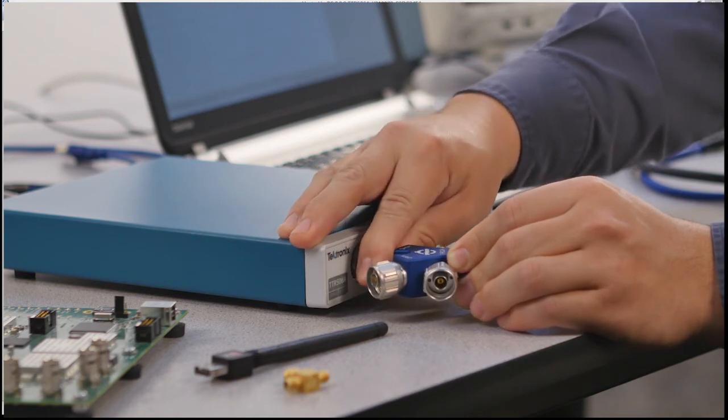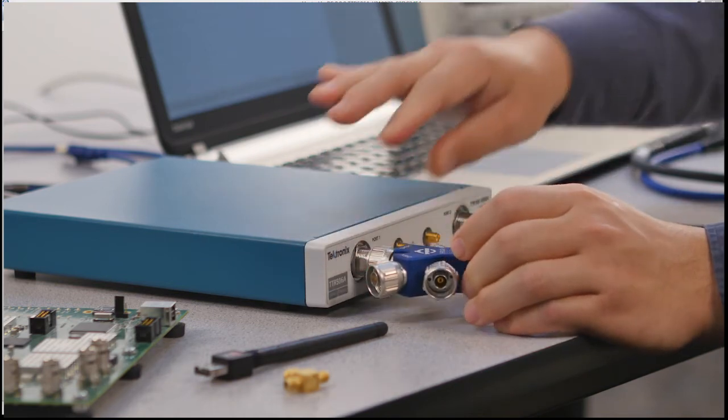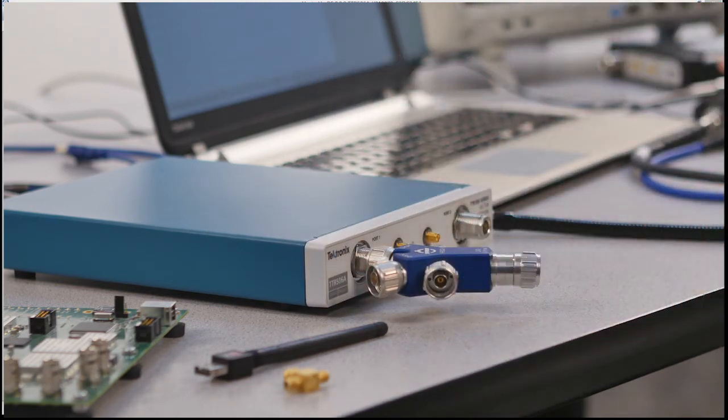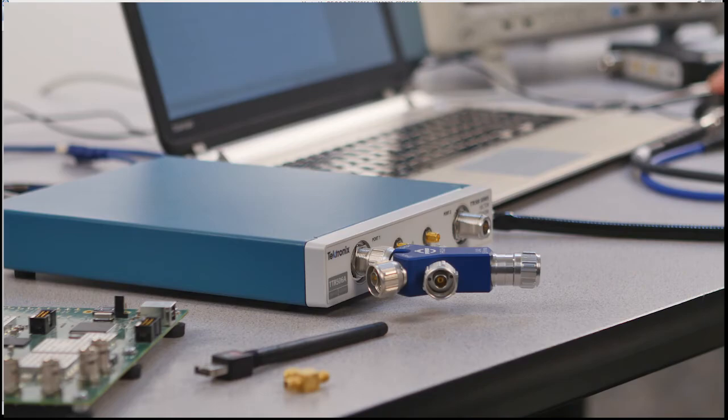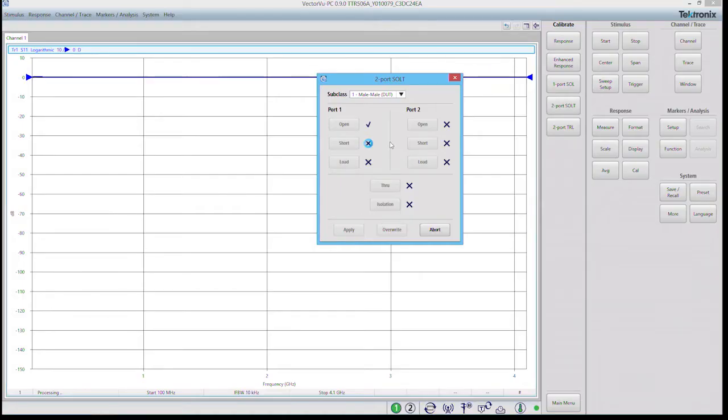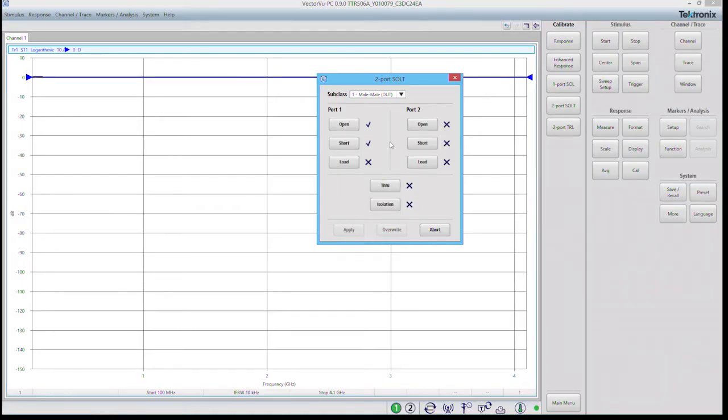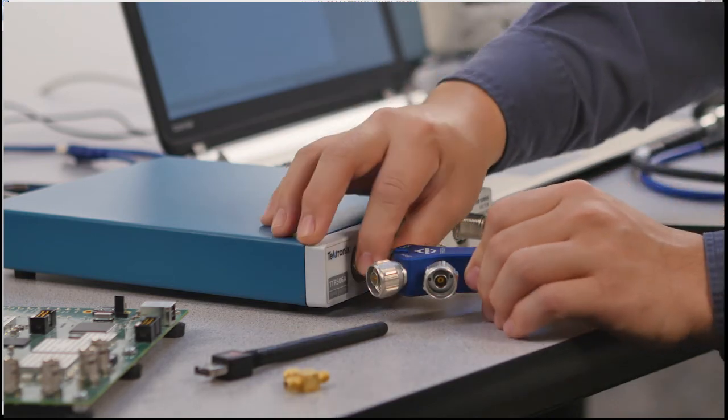Once that connection is snug, click short and then repeat one more time for port 1 load.